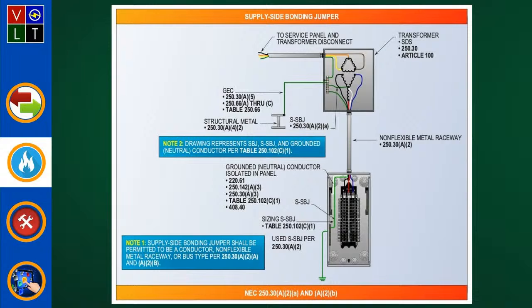And then we tell you the supply side bonding jumper shall not be required to be larger than the ungrounded phase conductors. Now, I want to point one thing out there. In order to have a supply side bonding jumper going down to that panel board, you have to make sure that bonding jumper is permitted to be of a non-flexible metal raceway or of the wire type or bus type, based on which requirements. This is what you have to pay attention to. Okay. It's a wire type, and if it is a wire type, it has to comply with what?